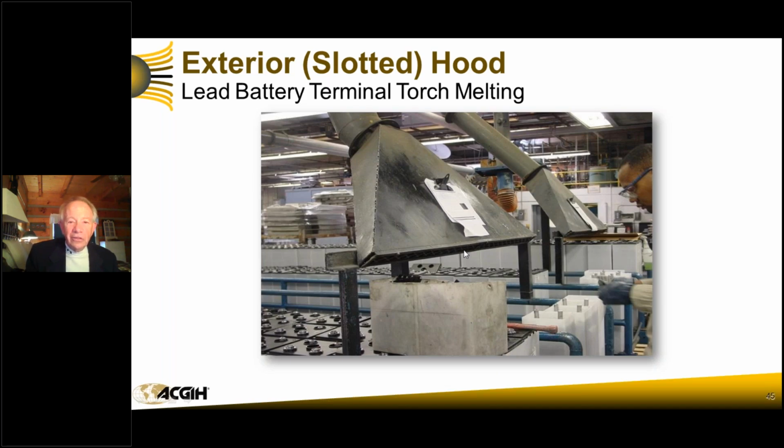So this is a little bit less resistance, but only a little bit. And in testing these, we'll have in excess of 90% of the velocity here, as we do with the shortest path. So we're still getting very effective capture even out here away from it as we are towards the middle, somewhat weighted towards the middle. That's a fishtail.